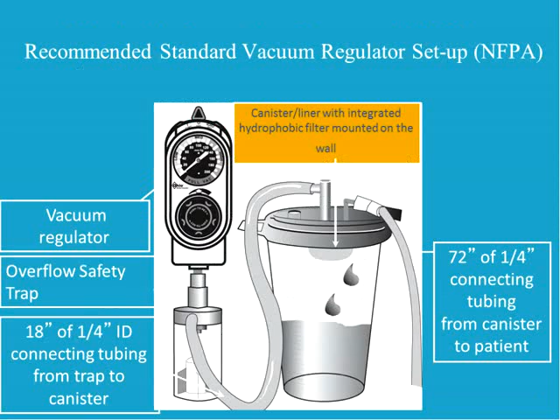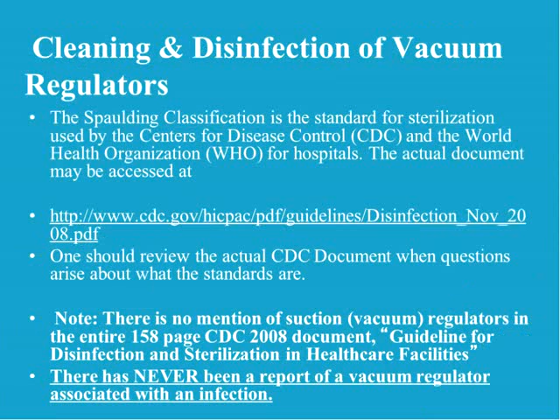There's been a lot of discussion about cleaning and disinfection of vacuum regulators. The Spaulding classification is the standard for sterilization used by the Centers for Disease Control and the World Health Organization. The actual document can be accessed at this website, and I would encourage one to review the actual document if questions arise. There's a lot of misinformation out there about where a vacuum regulator falls within this category of the CDC and the Spaulding classifications. There is no mention of a vacuum regulator in the entire document. And moreover, vacuum regulators are downstream from the patient. The patient's protected by the filter in the canister. And there's never been a report of a vacuum regulator associated with a patient infection.